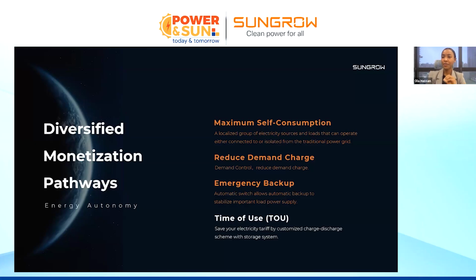Reduce demand charge. So this is the point where you are having demand, but perhaps it increases over time, or you add more load in future. So you can install your solar energy storage system to power up and take the demand of these loads. Emergency backup. In case there is load shedding or an urgent grid failure, the system will be there to energize and feed the load using the battery.